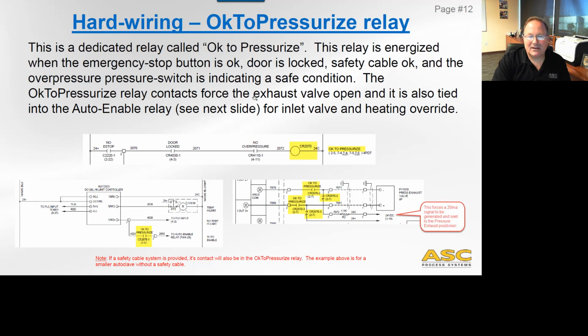The OK to pressurize relay contact forces the exhaust valve to open, and it's also tied to the auto enable circuit. So right here, there's an auto enable circuit which comes through the high limit controller, through the normally open contact of that high limit controller, which means that's safe, through the OK to pressurize relay and then over to the auto enable relay. We'll talk about the auto enable relay later. Now what you'll see here is the OK to pressurize is not only set up on the inlet valve, but it's also on the pressure exhaust valve.